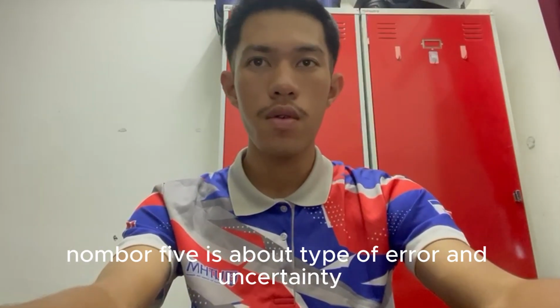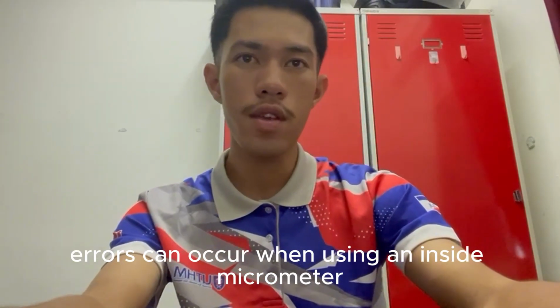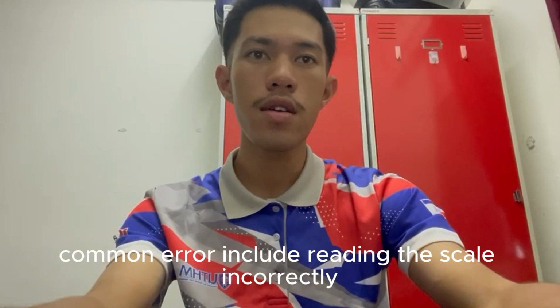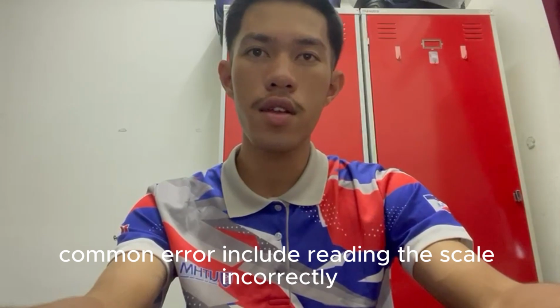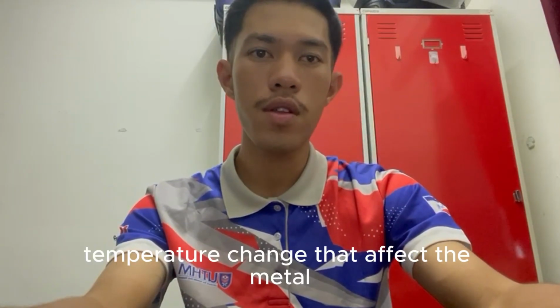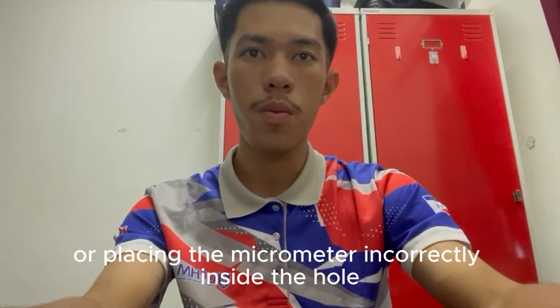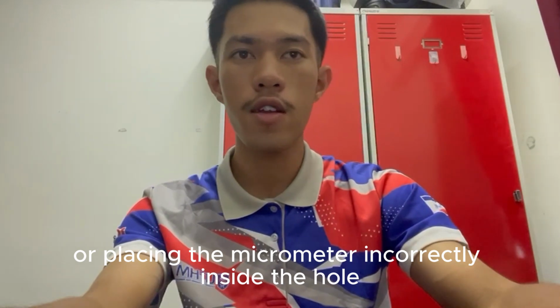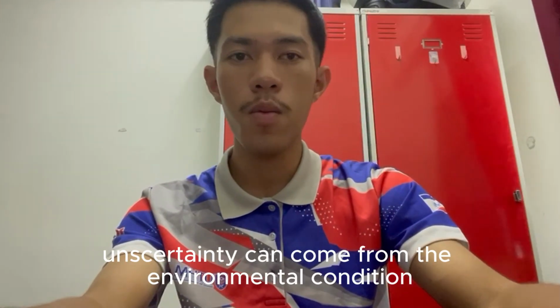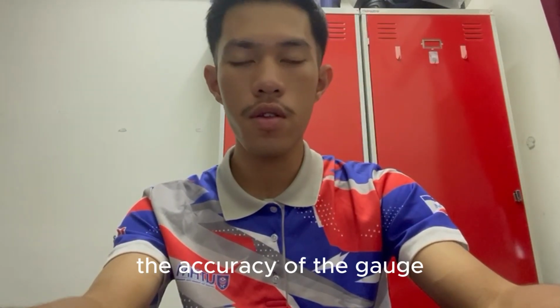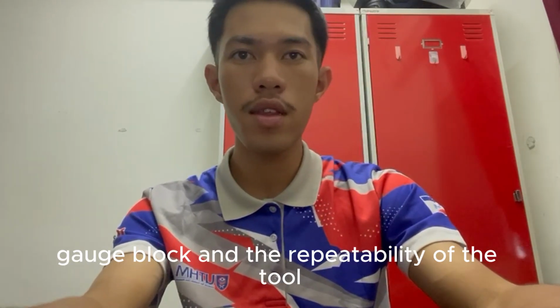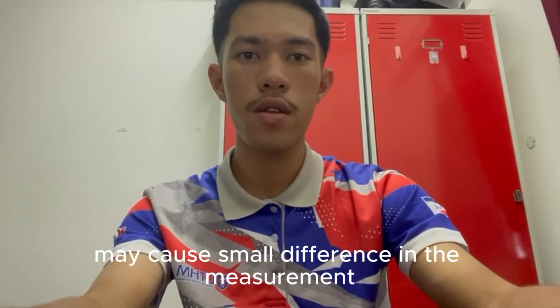Number 5 is about types of error and uncertainty. Errors can occur when using an inside micrometer. Common errors include reading the scale incorrectly, worn screw threads, temperature change that affects the metal, using the wrong measuring force, or placing the micrometer incorrectly inside the hole. Uncertainty can come from the environmental conditions, the user's skills, the accuracy of the gauge block, and the repeatability of the tool. These factors may cause small differences in the measurement.